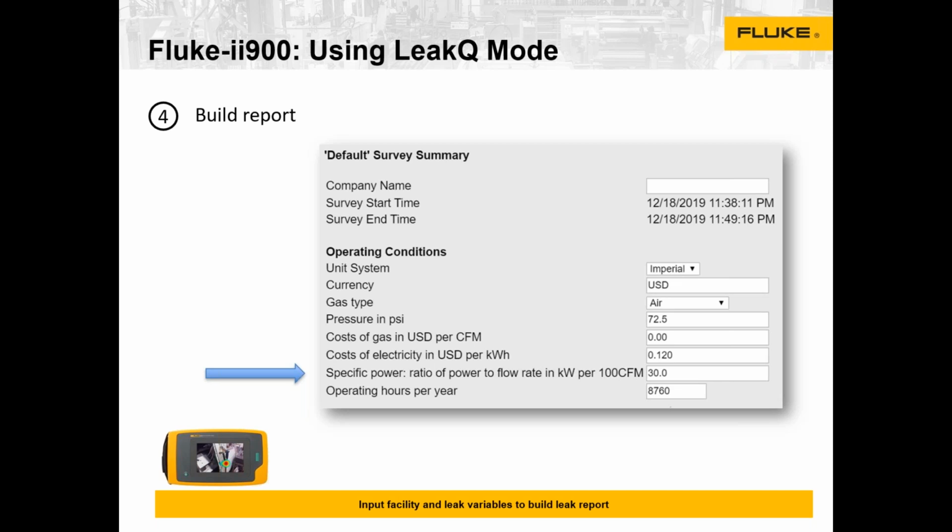I think that we've noticed that if you look up from a manufacturer, they're often over-speccing that, maybe more in the lower numbers. So it's kind of best case. If you don't want to have it like that, then you might want to scale back to about 30. The other thing is there are ways to calculate it over time. If you really want to know, you can look over a week or over a certain amount of time at how many kilowatts you had and how much flow you've had. So you can calculate it better if you want, but I'd start with 30.